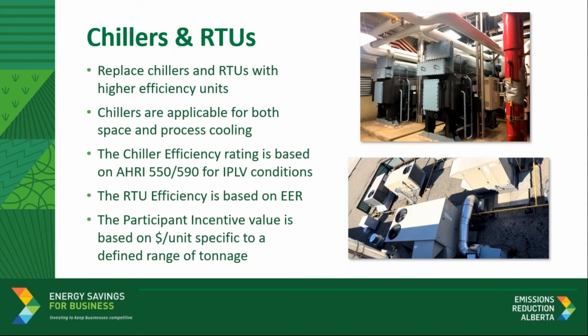What's the basis of the efficiency rating in this space? Chiller efficiency must meet or exceed the requirements of the AHRI 550/590 standard, and that's based on the integrated part load values, the IPLV. We have classified the efficiency requirements for several capacity ranges, and the incentive rates would be different for each category. For example, an air-cooled chiller with capacity anywhere between 50 to 150 tons would have to have an EER of 16.44 or higher.